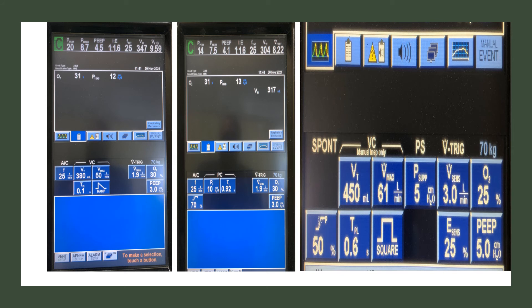Here you can see three screenshots of the ventilator monitor. This is assist volume-limited ventilation, this is assist pressure-limited ventilation, and the last one is pressure support. You can set ETS — seen here as E-sensitivity, which stands for expiratory trigger sensitivity — and you can set this value only on the pressure support mode, not on pressure-limited assist control or volume-limited assist control.